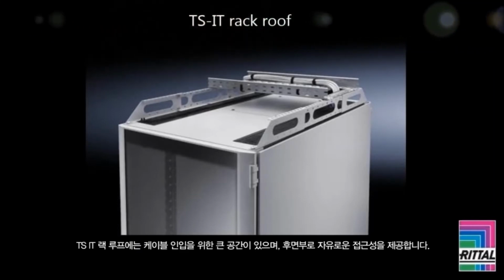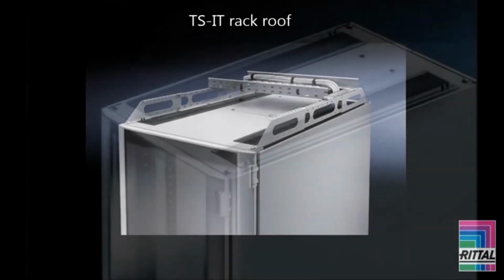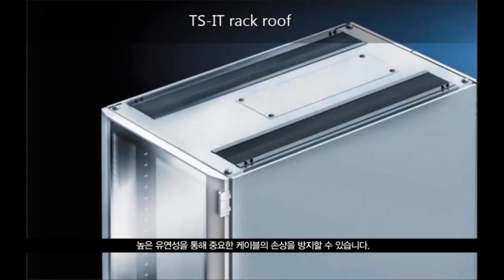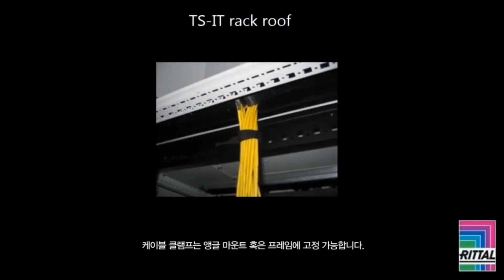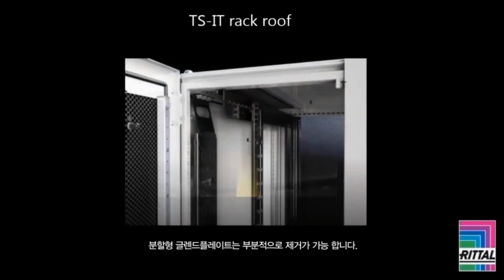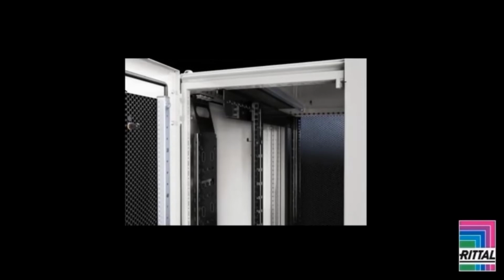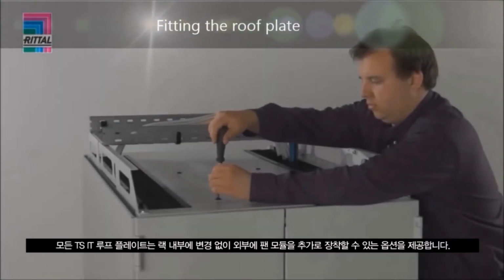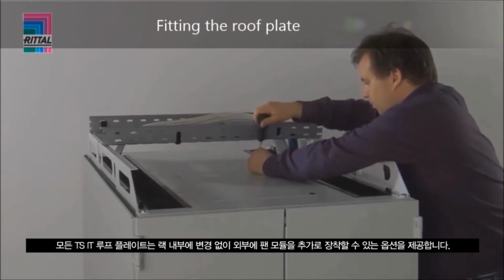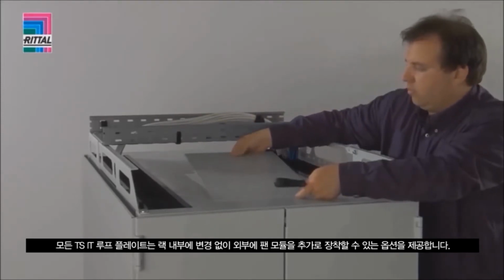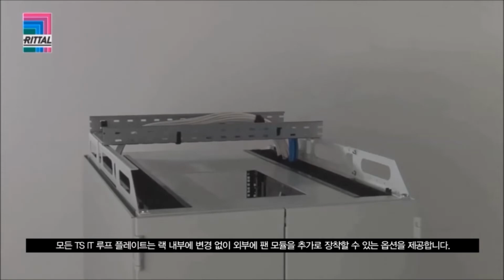The TSIT rack roof has maximum space for cable entry and free accessibility from the rear. High flexibility ensures sensitive cables are not damaged. Cable clamping is attached directly at the depth stay or the enclosure frame. The multi-piece gland plate can be withdrawn retrospectively. Every TSIT roof plate offers the option of retrofitting an external fan module without encroaching into the rack interior.